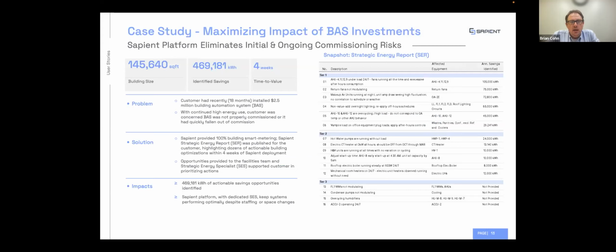This was about 6 weeks after they put in a $2.7 million BMS. They officially signed off on it being commissioned, but weren't seeing the energy usage reduction they thought they'd get. After we put our system in—no shutdown or anything like that—within 4 weeks we were able to generate this report. This is a 145,000 square foot facility, and we found almost 500,000 kWh that we were able to save.